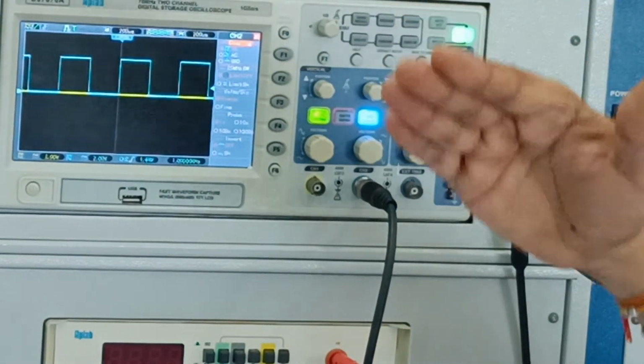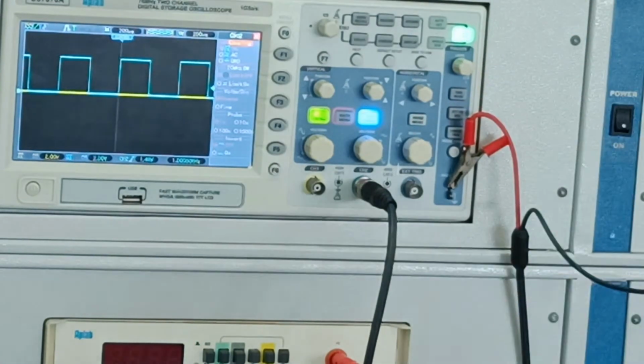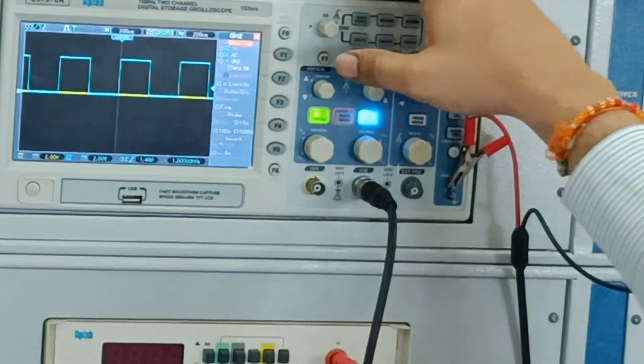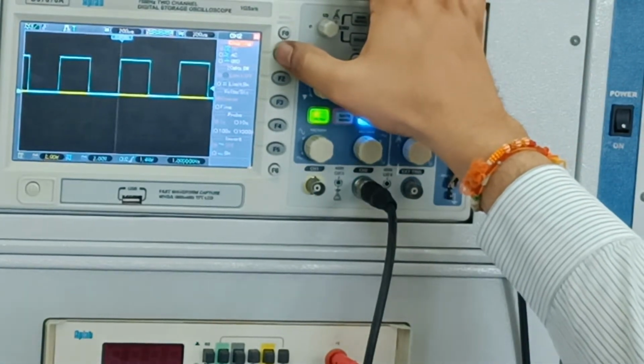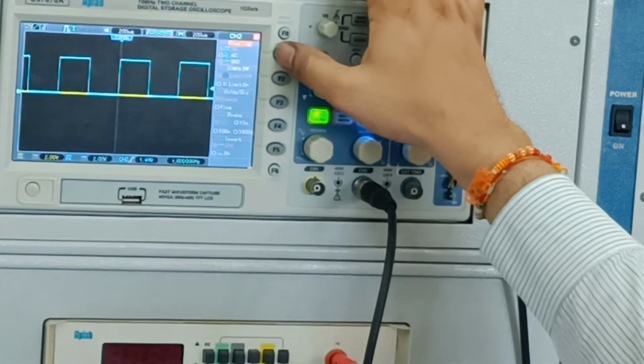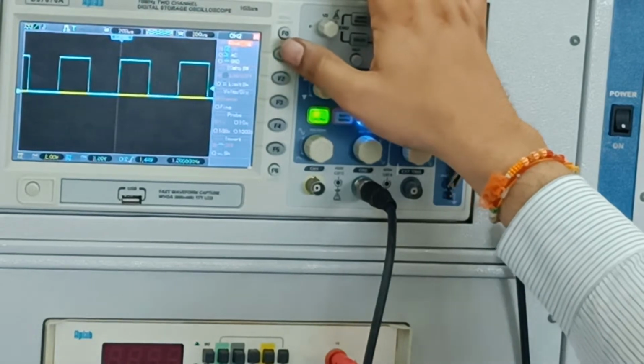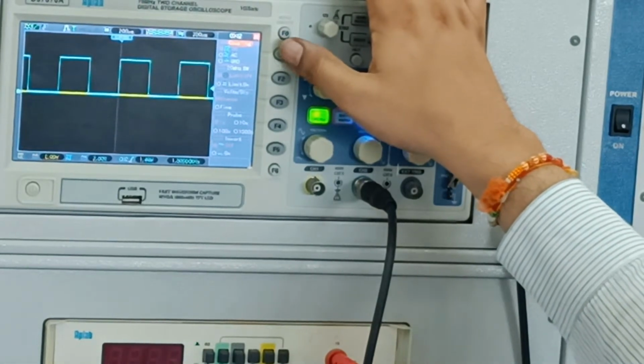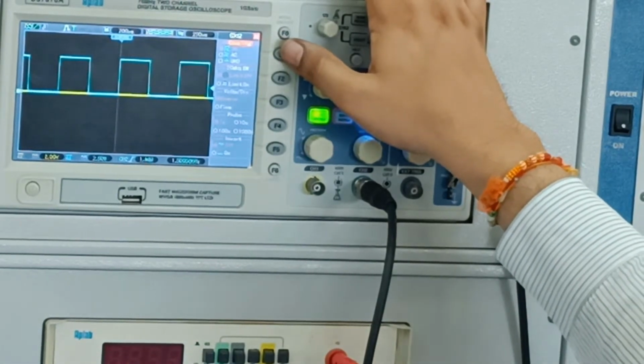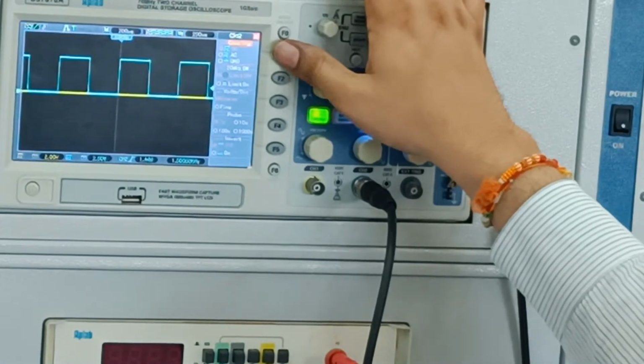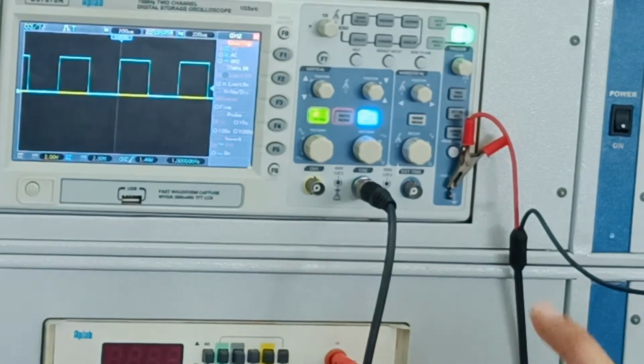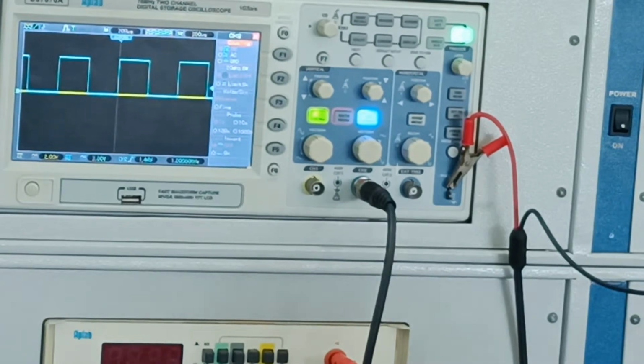So always make sure when you are doing waveform measurements, it is a good idea to check whether this is in DC mode or AC. Ideally, it should be in DC mode. That will tell you whether you are going between 0 to 5 volts or between minus 2.5 to 2.5, or whatever range you are going. In AC mode, whether your actual signal is between 0 to 5 volts, or minus 2.5 to 2.5, or minus 5 to 0, all are 5 volt amplitude. They will all display the same.